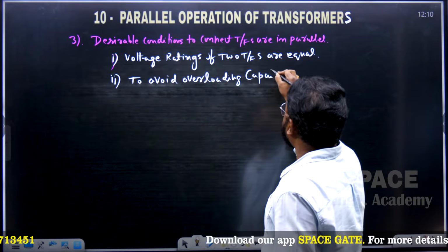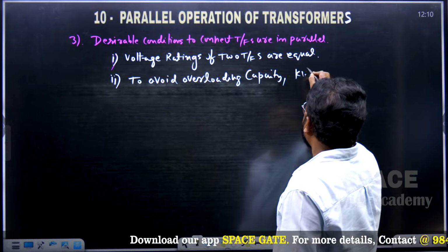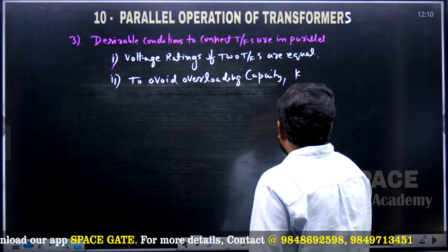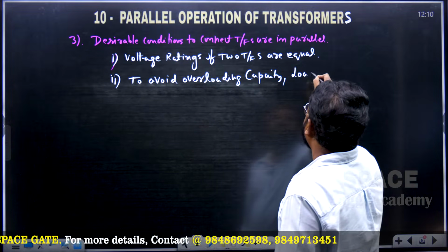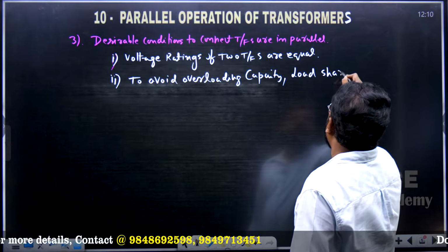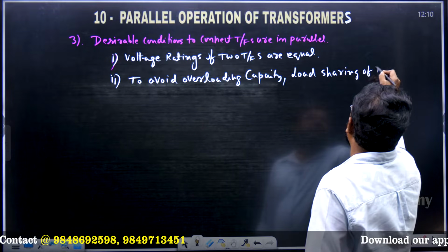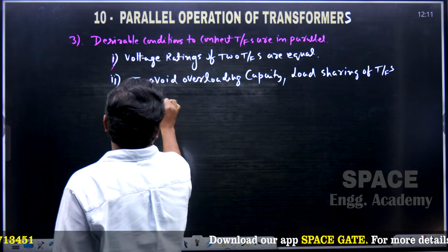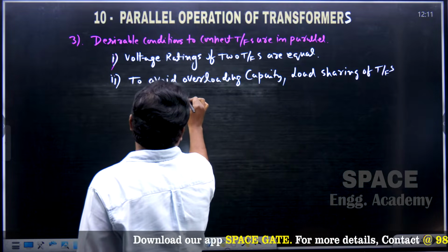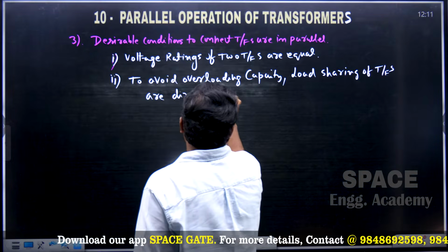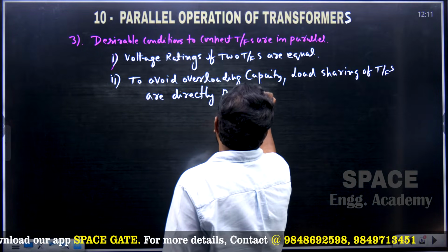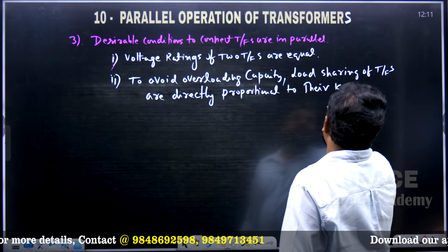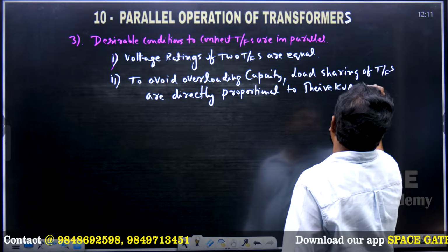So another condition here: the load sharing of the transformers is directly proportional to their kVA ratings, directly proportional to their kVA ratings.